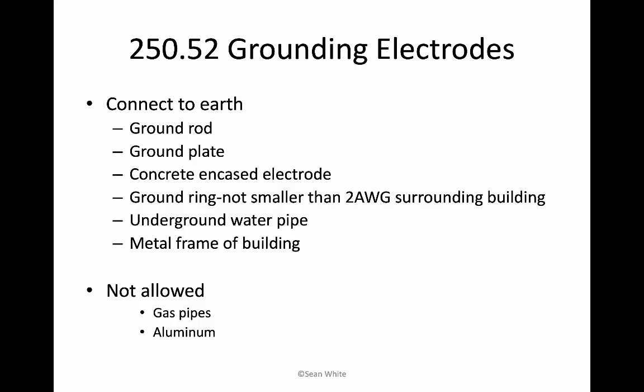250.52, grounding electrodes connecting to earth. And there's different types, like a ground rod, which we were just looking at. There's a ground plate, which has the same surface area as a ground rod. And I've seen those used a lot in Canada. It's kind of weird. It's a Canadian thing, but it's in the NEC. There's a concrete encased electrode, which is super popular when you're pouring the foundation of a building or a foundation for a big inverter pad. You can just put copper right inside of that concrete, and that connects you to ground.